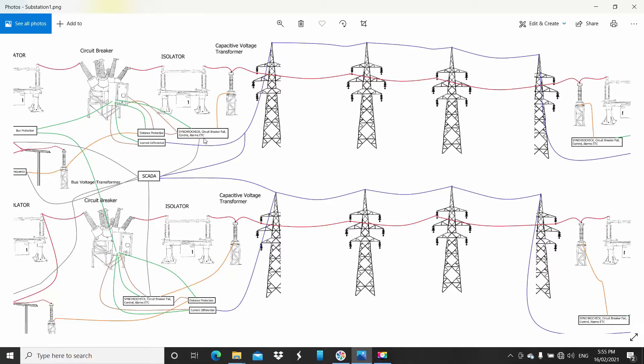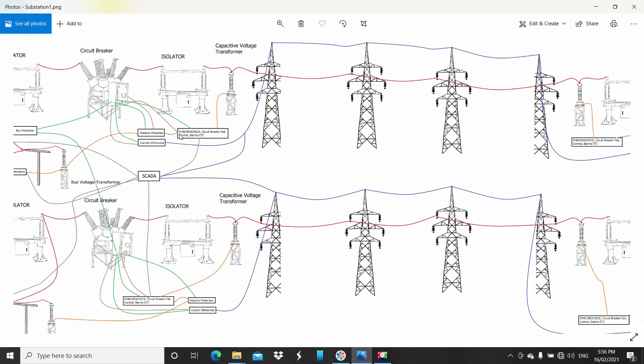I've got a distance protection relay, often called an impedance relay. You can see its connection: green is CT connection, orange is VT connection, and brown is control. For the synchronization check circuit breaker management relay, I've got a second control signal. That control signal, if this one couldn't act, would send a trip signal off to the other relay, the circuit breaker management relay, and that would also try and trip.